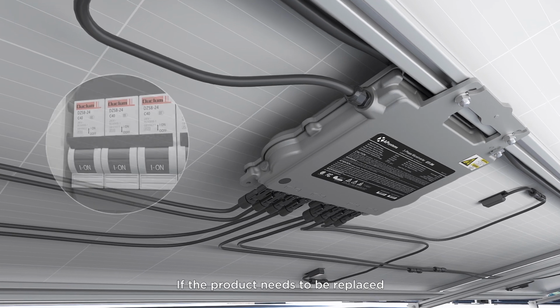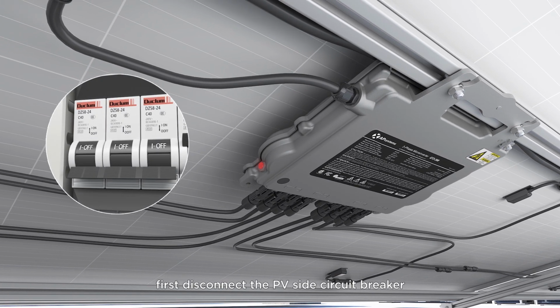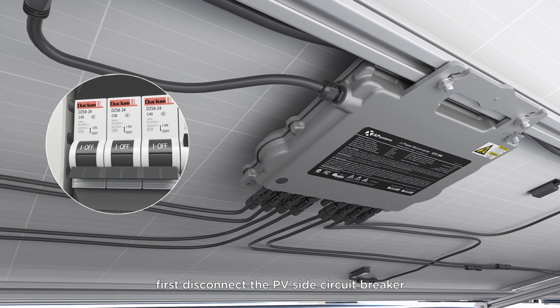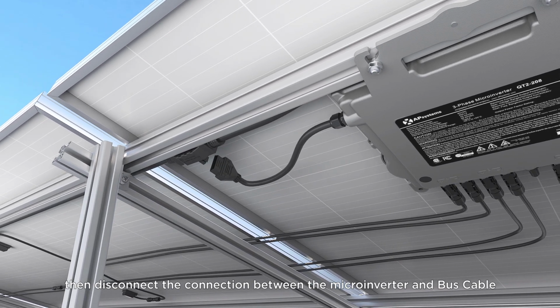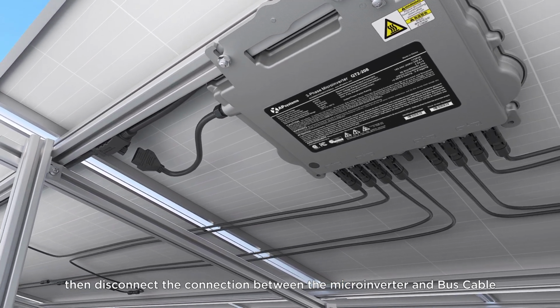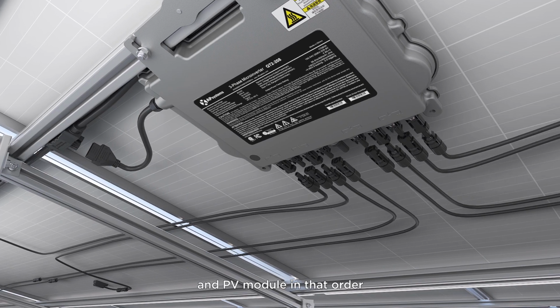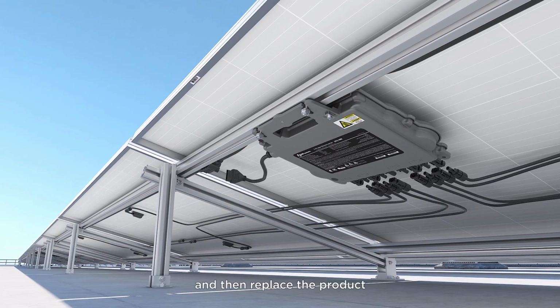If the product needs to be replaced, first disconnect the PV side circuit breaker. Then, disconnect the connection between the microinverter and bus cable and PV module in that order, and then replace the product.